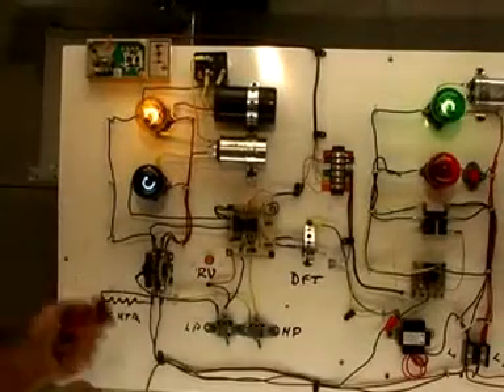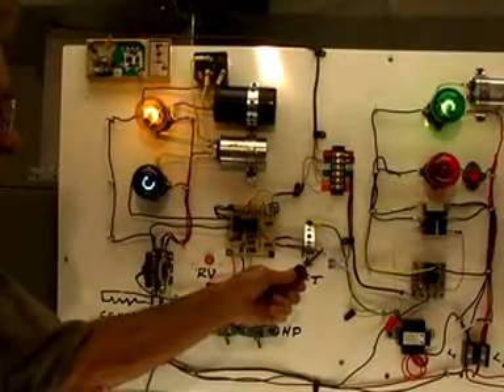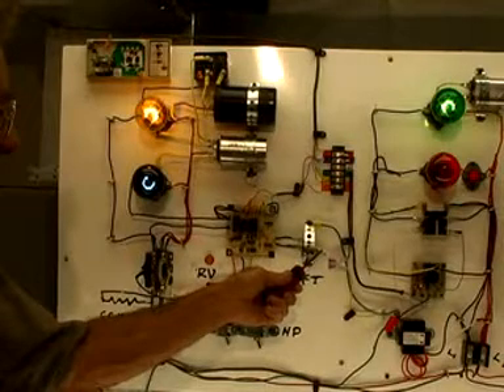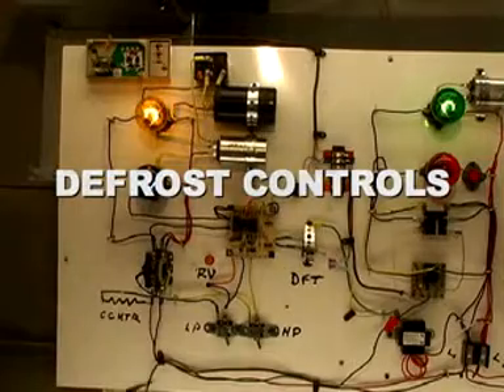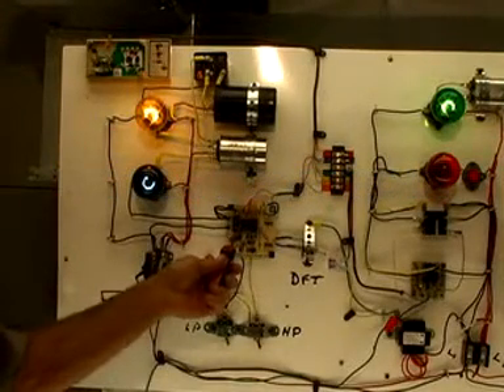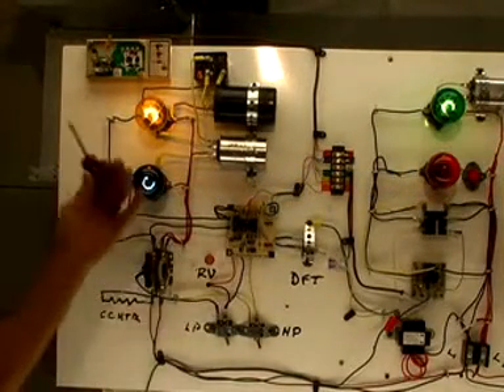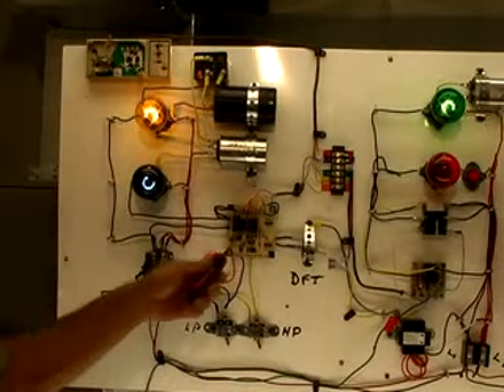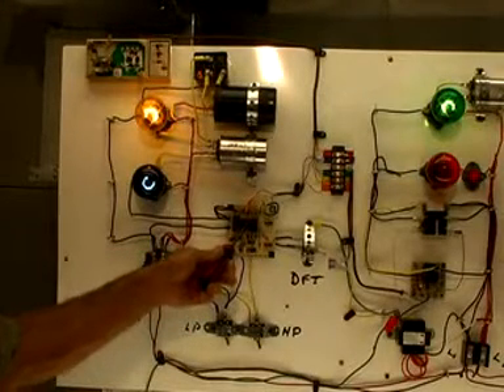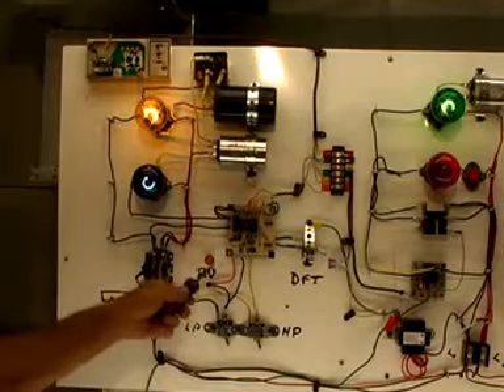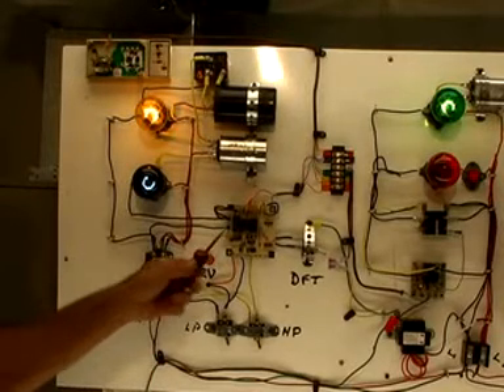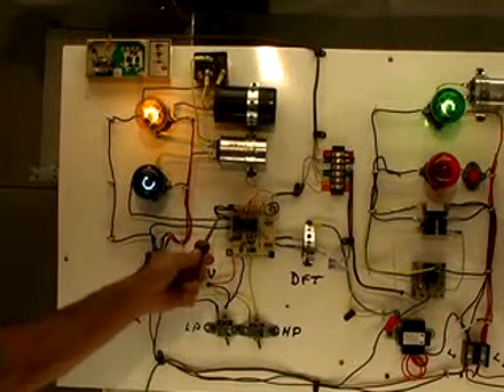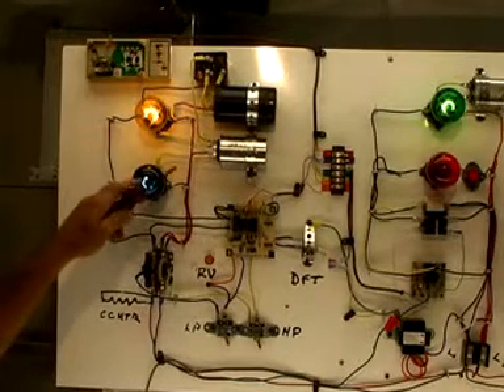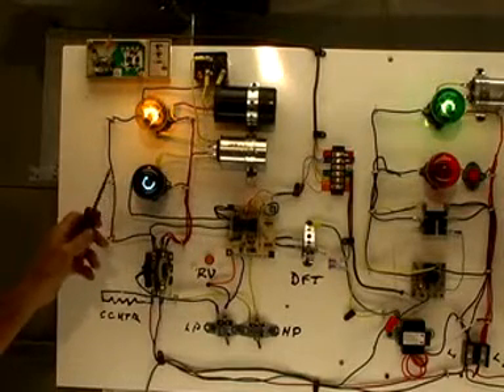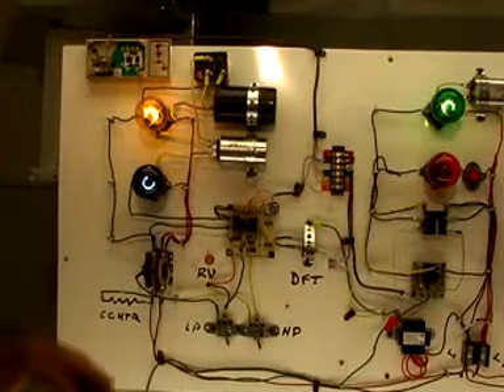Okay, we're still in first stage heat. Now the little on-off switch I've got simulating the defrost limit switch, when the toggle's down, it's in the closed position. So if we come up here to the test pins on the defrost control and short across them, then if all this does what it's supposed to do, the board is going to initiate a defrost cycle. What you're going to see then is the reversing valve will light back up. The blue light's going to go out because this relay is going to open up the circuit between these two wires, effectively cutting the condenser motor off. And then of course the red light will come back on.